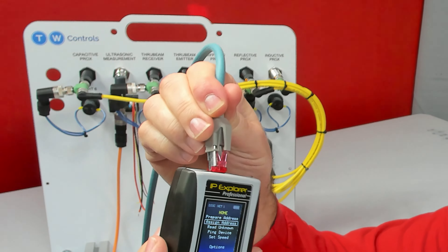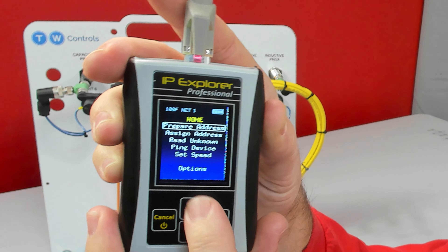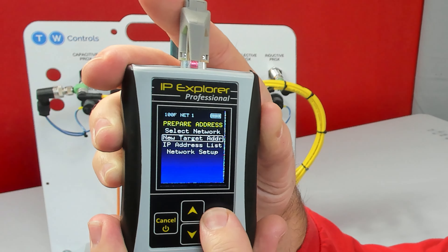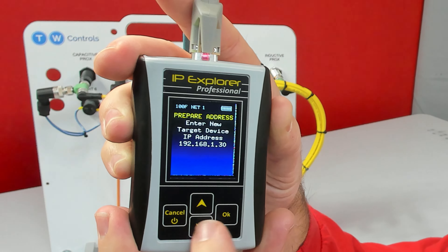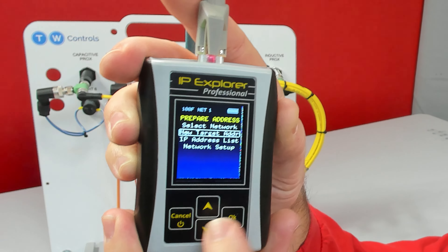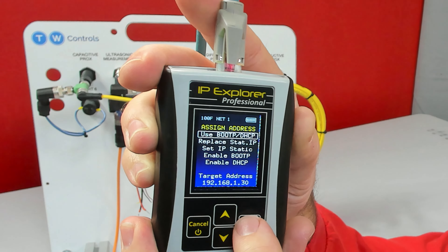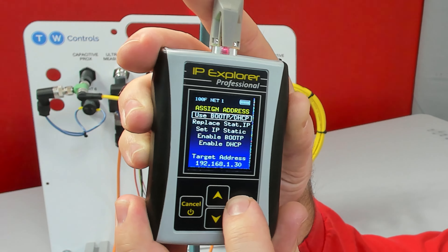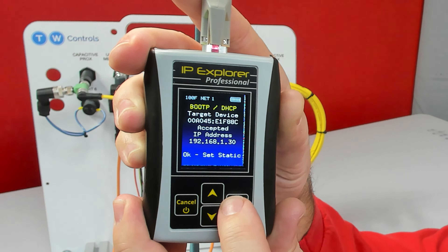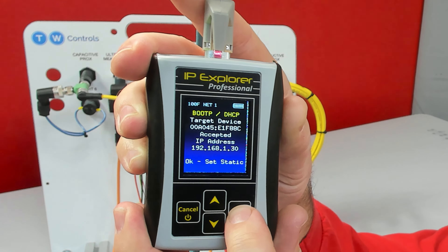You can plug directly into the IO-Link device. The first thing I need to do is set my target IP, so I'm going to go up to Prepare Address and go down to New Target IP. Here's where I set my target — I want it at 192.168.1.30. Now I'm going to go to Assign Address and use BOOTP/DHCP. It accepted the address, and I can press OK to set it to static.